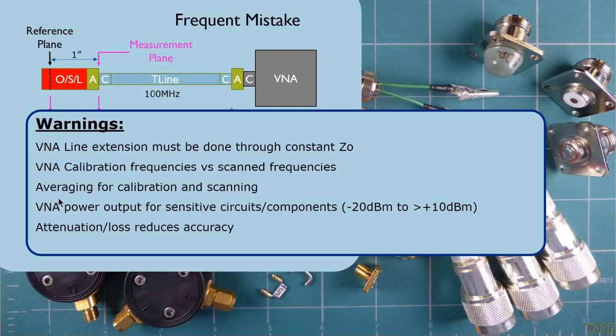But the other thing to keep in mind is averaging whenever you're doing the calibration. A lot of analyzers do a lot better job if you average. So instead of taking a calibration point once, you make 10 measurements and average those for the calibration point. And then when you scan it, you take 10 measurements and average that number. That gets rid of some of the noise in the analyzer, which again is another way to improve your measurement accuracy without buying a more expensive analyzer.